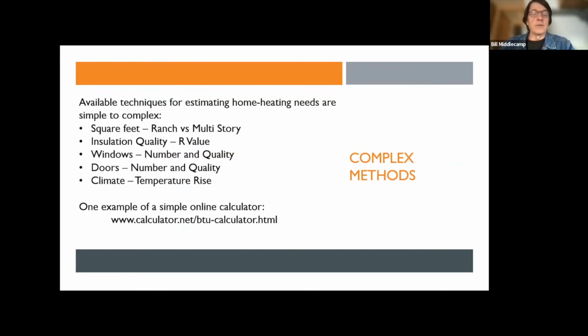So the typical ways that heating needs are calculated by contractors is to look at how many square feet you have, and if it's all on one level, that's one calculation. If it's 2 stories, well then you don't have to heat the floor between the floors, and so you have factors for that. You have to look at the insulation quality, look at the quality of the windows and how many of them there are, how many doors you have and how good are they. And you have to, of course, take into account the temperature rise or the climate conditions. These can get really complicated, and my contractors really didn't want to do that. So they just said, well, you had 145,000 BTU before, we're going to give you 145,000 BTU as a replacement.